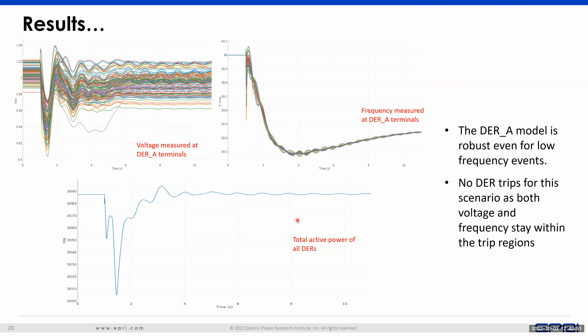But if you have a fault and then trip the event, you see a lot of DER tripping. The question to ask here is whether this tripping is expected. If a transmission planner is running this simulation, the first thought that may come to mind is, this model isn't showing the behavior we expect, so the model must be wrong.